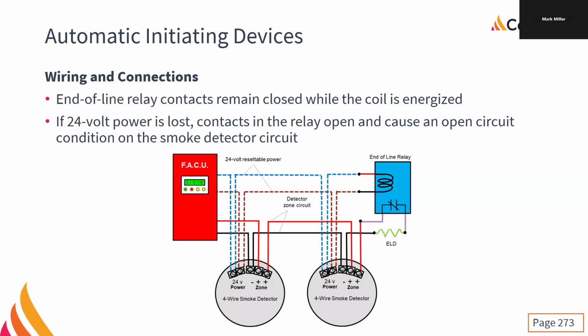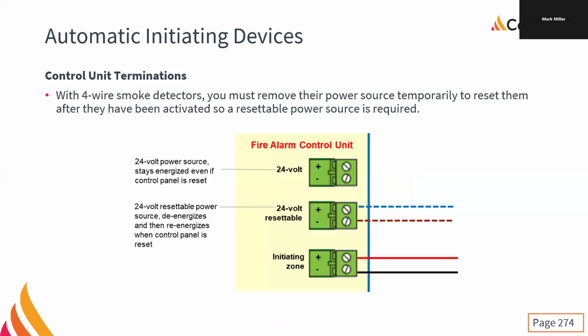And you'll see that on these devices, the initiating zone is directionally sensitive, right? The positive goes in on the left and out on the right, in on the left and out on the right. The negative is not directionally sensitive, just the positive. And so we can see we have 24 volt power, and it's working. So the end of line relay coil is energized, so that contact is closed, and so we get our end of line resistor working, and so we have our supervisory current. All is right in the world.